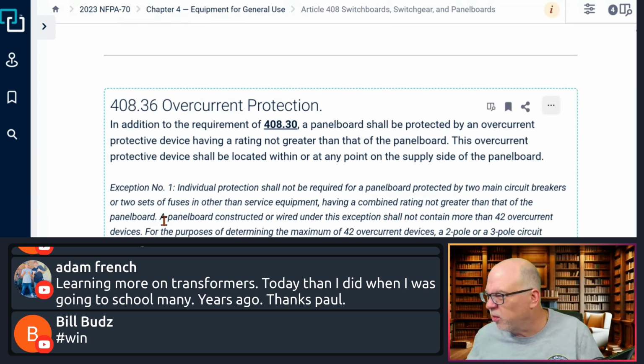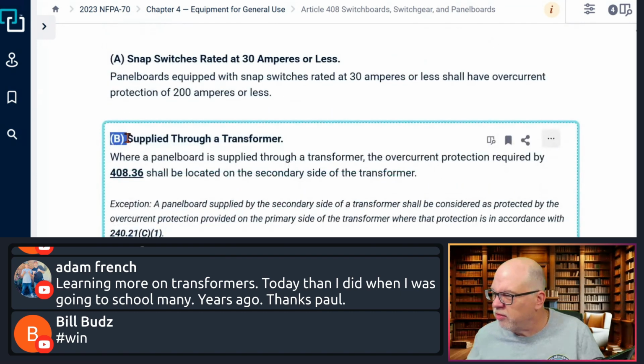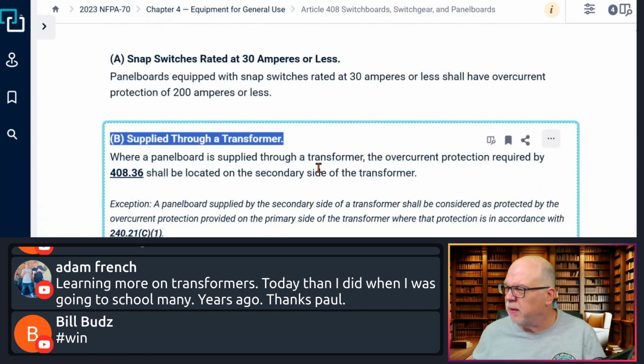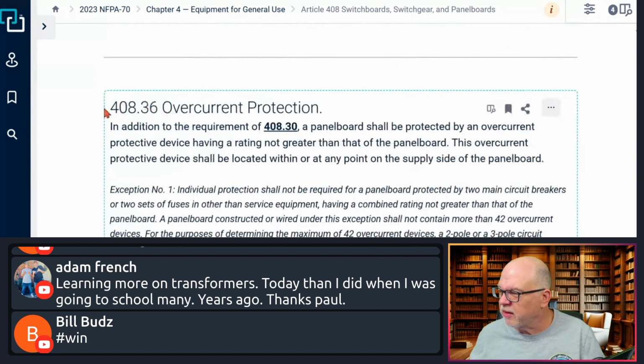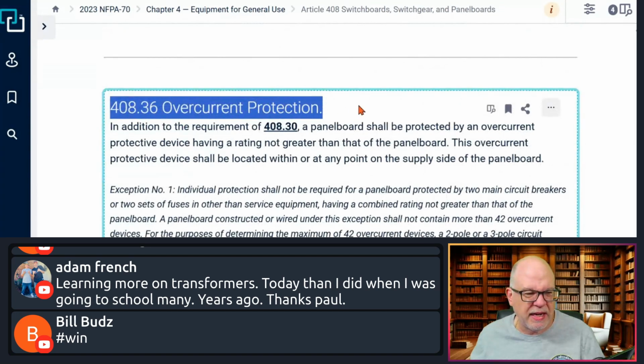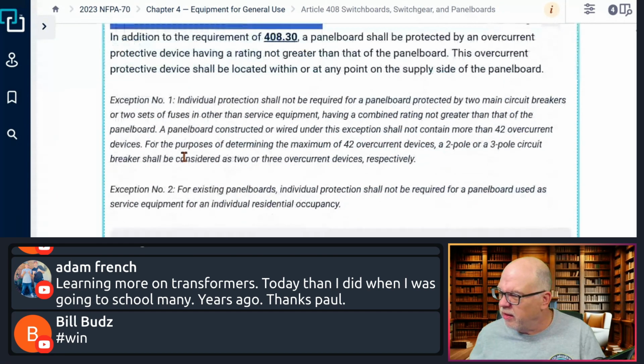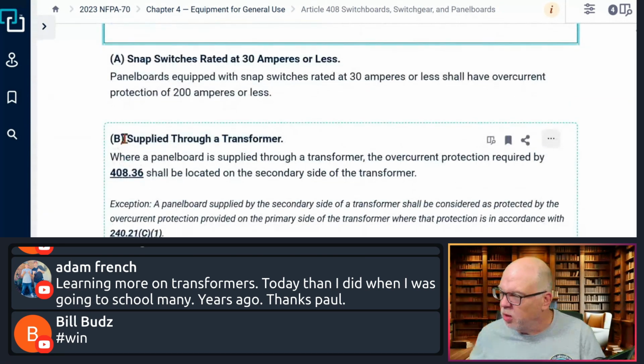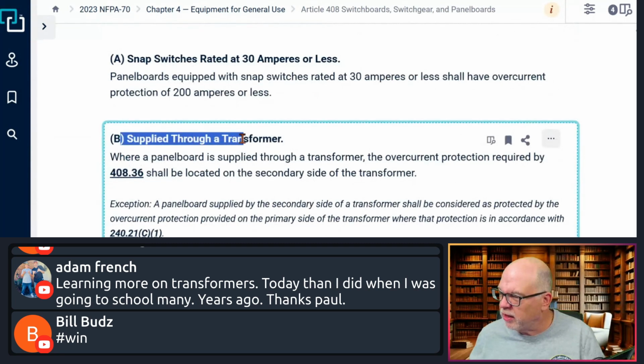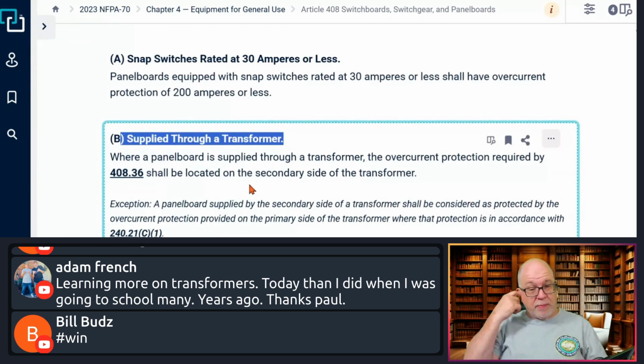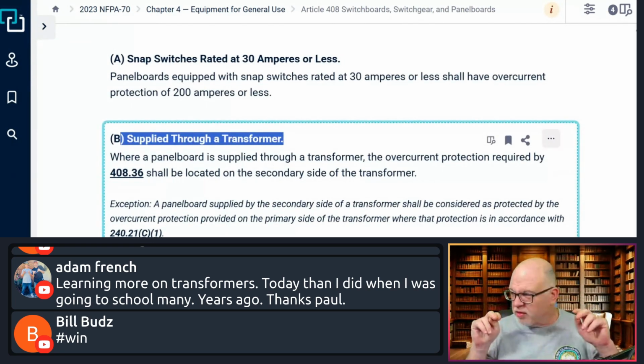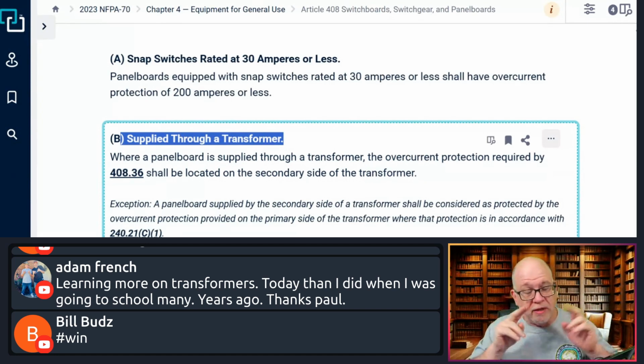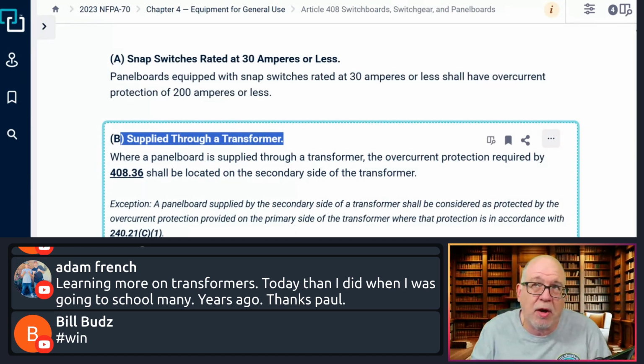Okay. Anyway, so we're looking at this one, B, we're talking about. Remember, we're under the overcurrent protection. We're in 408. This is something you may not be aware of, but this one is specifically when it's supplied through a transformer. So where the panel board is supplied, y'all saw me talking about the exception or the allowance. Where the panel board is supplied through a transformer, which is probably almost 10 times out of 10 what you're going to have. All right.